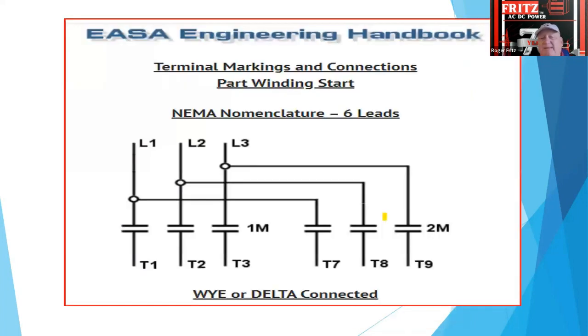There were many things back then where they said, okay, in order to reduce that inrush current so they didn't have to have bigger fuses and the power transformers and the generators had to be big, they did what they call part winding start. They would take literally half of the winding, start it, and then kick the other half in after it was running. Part winding starters, you still run into them, especially in the irrigation industry. There's a lot of those still out there.